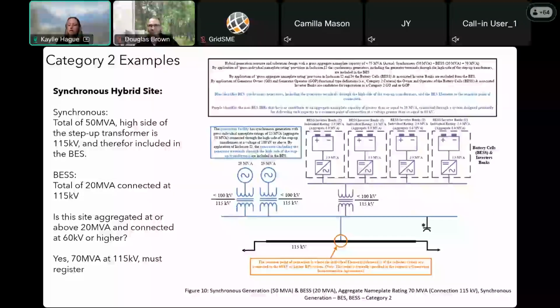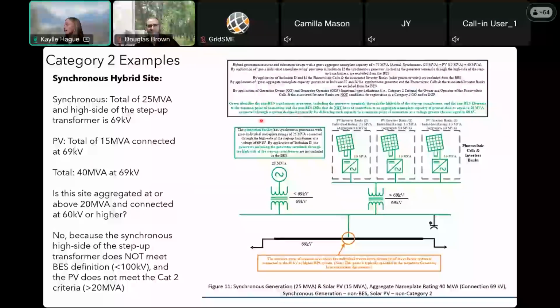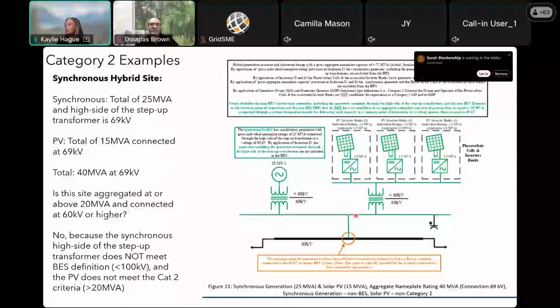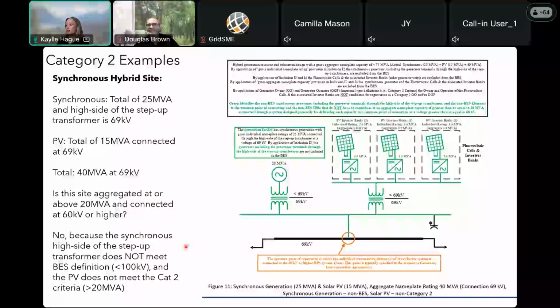Let's look at another one. So again, a synchronous hybrid site. This time, the synchronous side is only 25 MVA and it's connected below 69 kV. So the synchronous alone does not meet the BES definition, and that's because it's below 100 kV. If we look at that GO-IBR side, we see we have 6 inverter banks individually rated at 2.5 MVA. So 15 MVA connected at 69 kV. This alone does not meet the GO-IBR Category 2 requirement. And even though it's aggregating with the BESS side, NERC says this doesn't count because it still does not meet the BES definition over here. So together, even though we're at 40 MVA at 69 kV, you do not have to register as a Category 2.